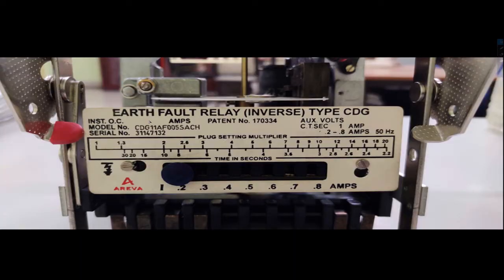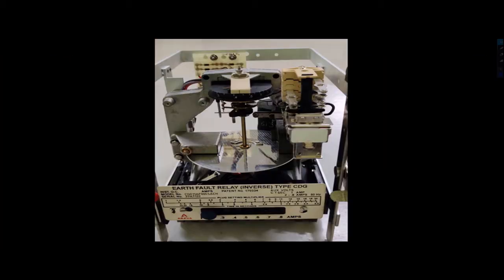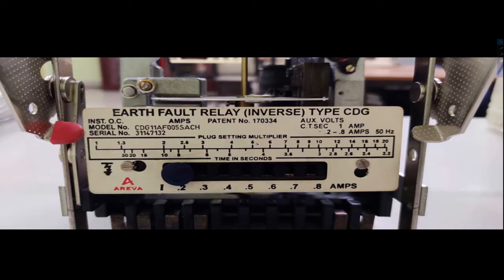Coming to this one, this is the nameplate of the relay. As per the name, it is the earth fault relay, and this is the inverse type relay. The type of the relay is CDG. C means it's a current operated relay, D means disc type, and G means IDMT characteristics relay. As it's a current operated relay, to actuate the relay we need to give current as an input. D means one aluminum disc is there, so if the current is more than the preset value, the aluminum disc starts rotating and generates the trip signal. And G means it follows the IDMT characteristics. Later on I'll explain what the IDMT characteristics of the relay are.